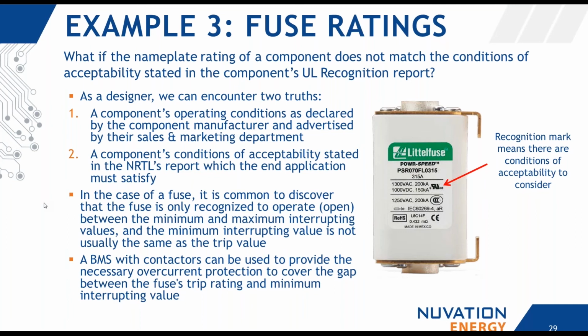To give an example, not this fuse, but a fuse rated to 400 amps with a maximum breaking current of 100,000 amps would be a good choice for a battery stack that in its typical application is only operating at 75% of that. But according to the conditions of acceptability, when we were reviewing it, we could discover that the minimum interrupting value is actually 5,000 amps. And so we need an overcurrent protection device in between to open at 400 amps. A BMS that's recognized to provide that overcurrent protection, if it's been evaluated as part of its functional safety investigation and paired with contactors that are rated for the application, can meet that functionality.